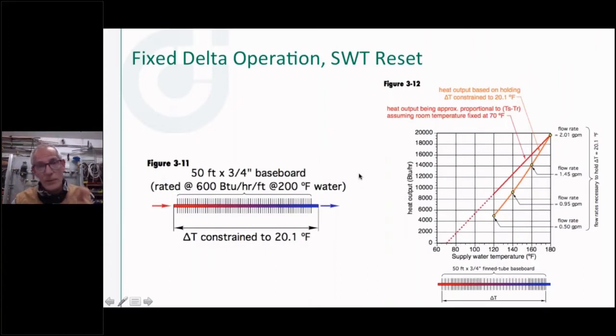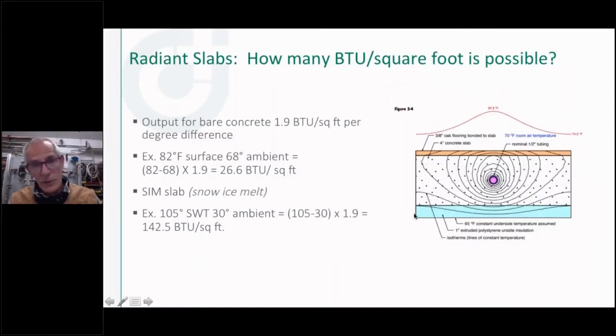It might take a couple of trips back to get that number, but you should be able to modulate that boiler pretty much from a design day down to whatever the lowest turn down rate is and exactly match the loss of the load on that building. So I prefer to modulate the temperature as opposed to modulating the circulator speed, especially if you're using outdoor reset control, because they're kind of trying to fight one another.